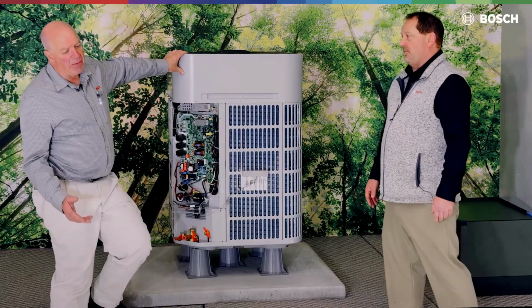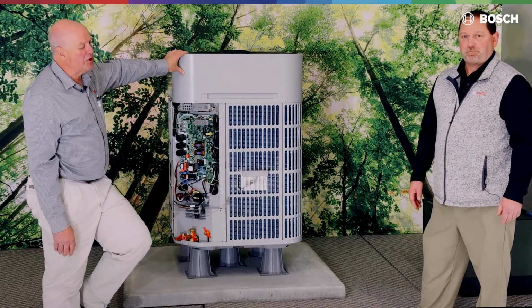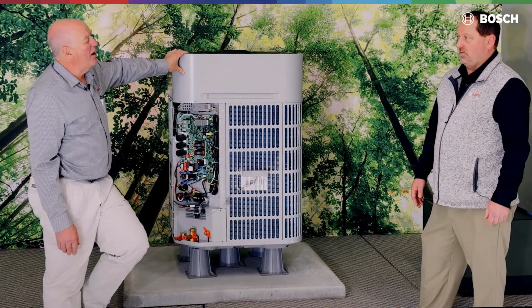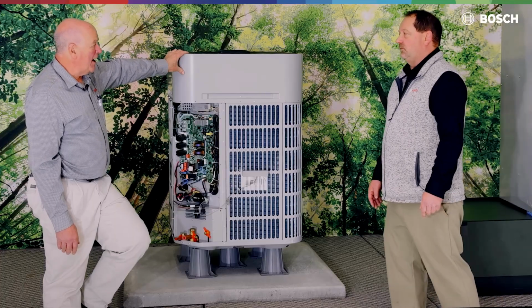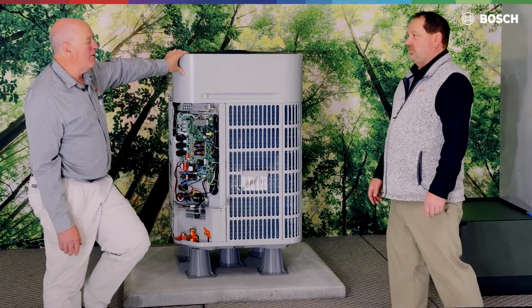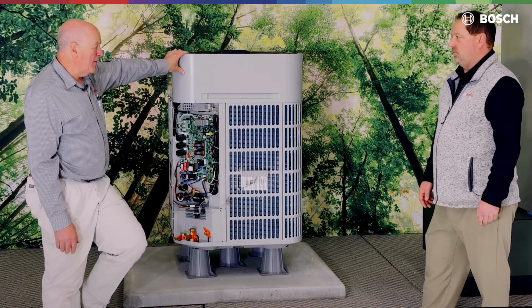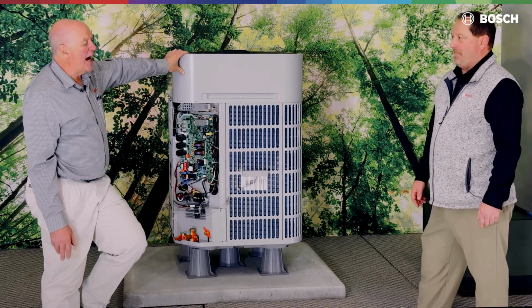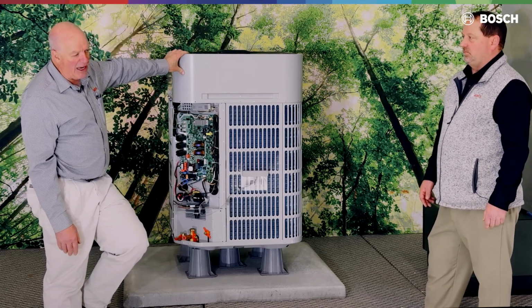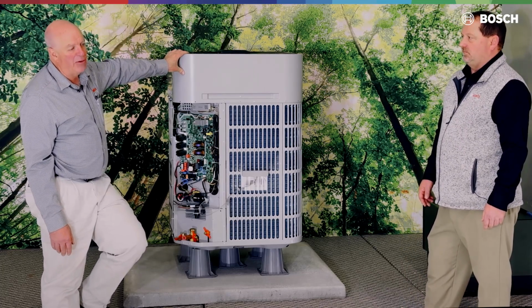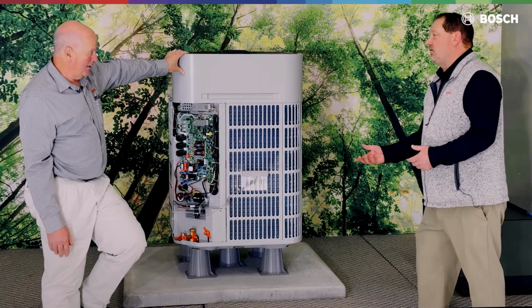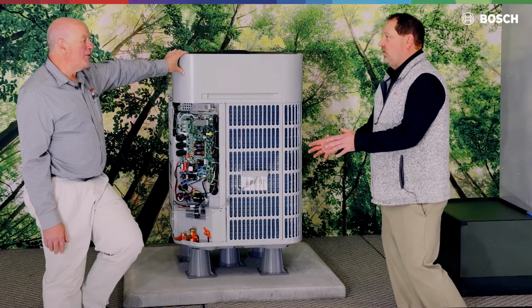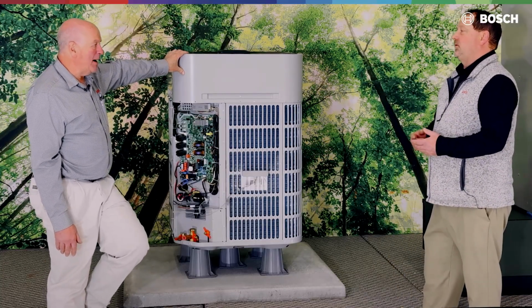After we're done with that pressure test and we did our soap to make sure there are no leaks, we're then going to go with our vacuum. We're going to hook up a vacuum pump. We're going to pull down to at least 350 micron. Now, 350 micron, guys, probably could take an hour or two at tops. If it takes over an hour or two, then your vacuum pump might really suck. So we're talking deep vacuum. 350 micron, that's deep. It's not 50 micron, but 350.